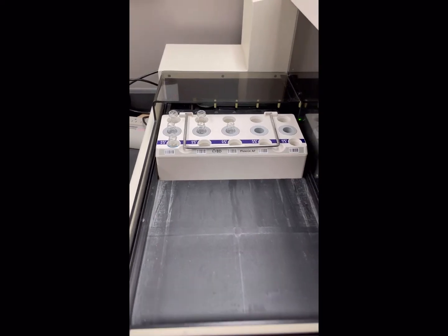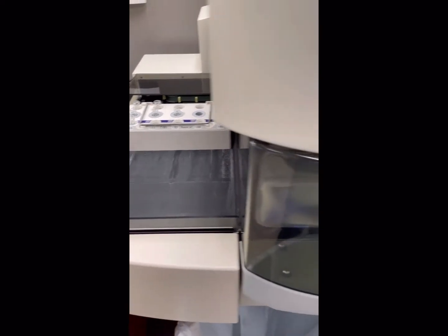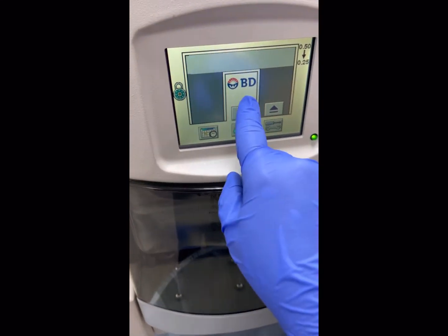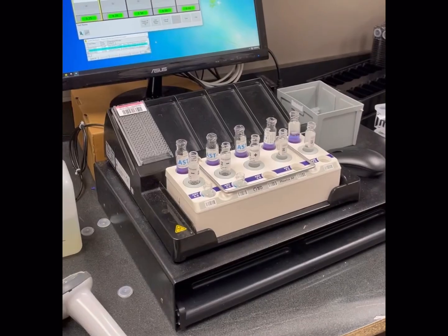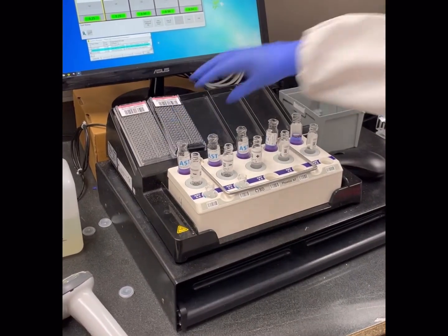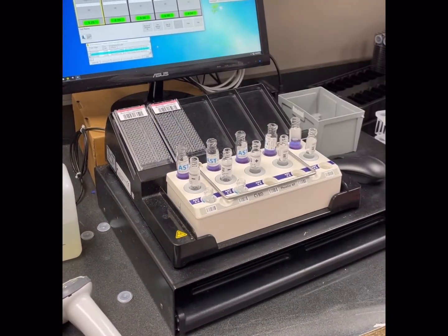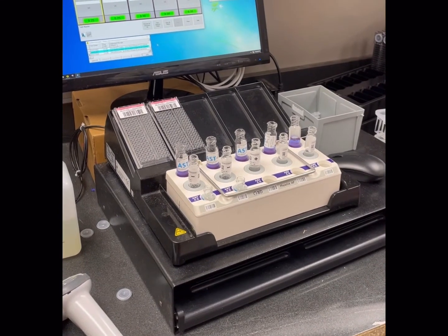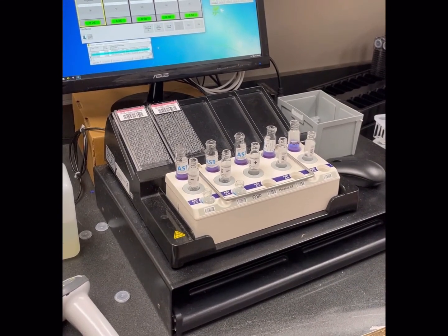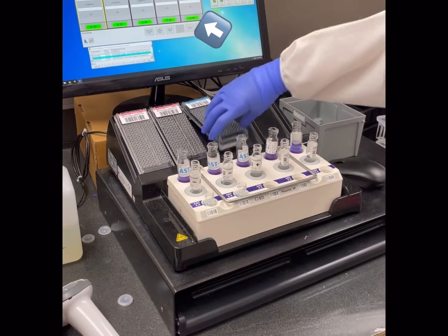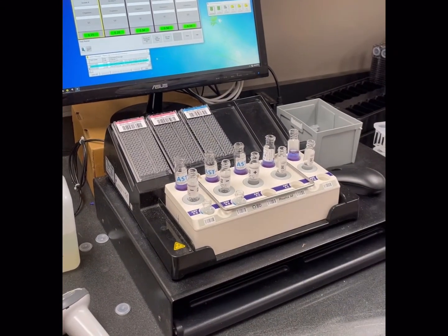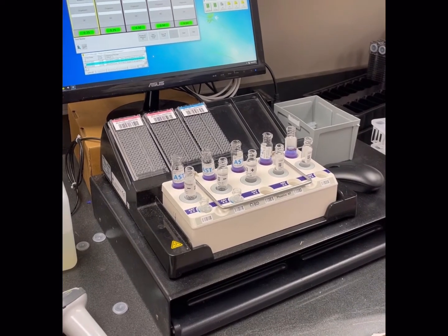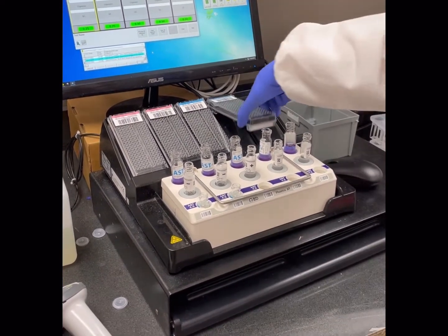Remove all of the caps on the tubes, place the rack on the conveyor belt on the left side of the AP, and press the play button on the screen. Once the rack is finished processing, place the rack on the inoculation station. All of the tube density measurements at the bottom of the login screen should be green and read 0.25 or 0.5. Unwrap the panels and place them on the inoculation station with the barcode facing up.